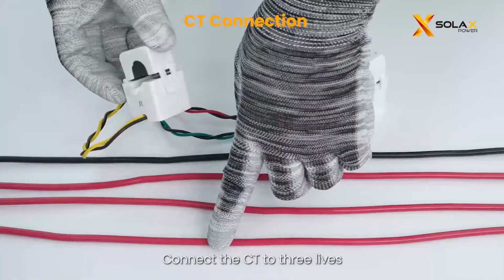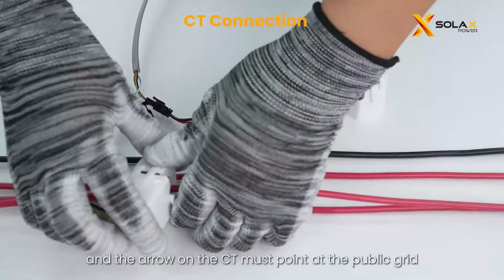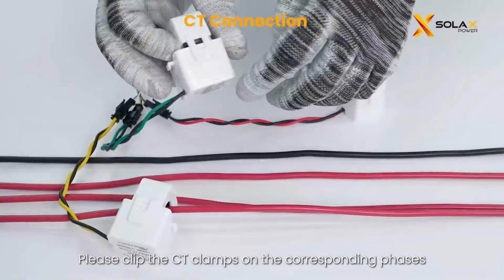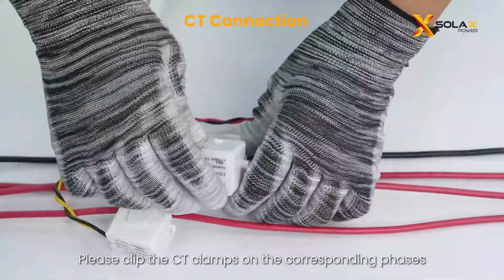Connect the CT to 3 lives, and the arrow on the CT must point at the public grid. Please clip the CT clamps on the corresponding phases.